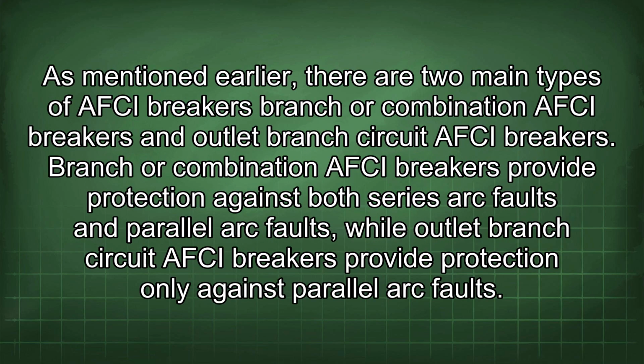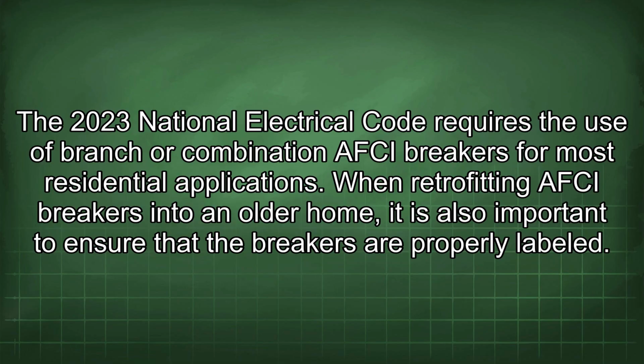As mentioned earlier, there are two main types of AFCI breakers: branch or combination AFCI breakers and outlet branch circuit AFCI breakers. Branch or combination AFCI breakers provide protection against both series arc faults and parallel arc faults, while outlet branch circuit AFCI breakers provide protection only against parallel arc faults. The 2023 National Electrical Code requires the use of branch or combination AFCI breakers for most residential applications.